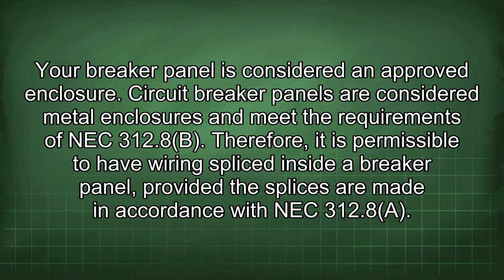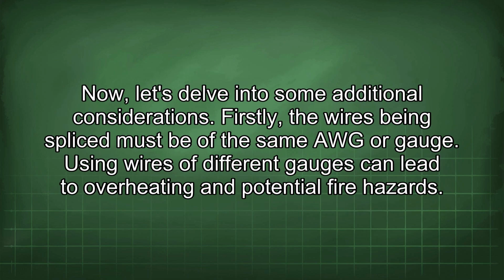Therefore, it is permissible to have wiring spliced inside a breaker panel, provided the splices are made in accordance with NEC 312.8a. Now let's delve into some additional considerations.